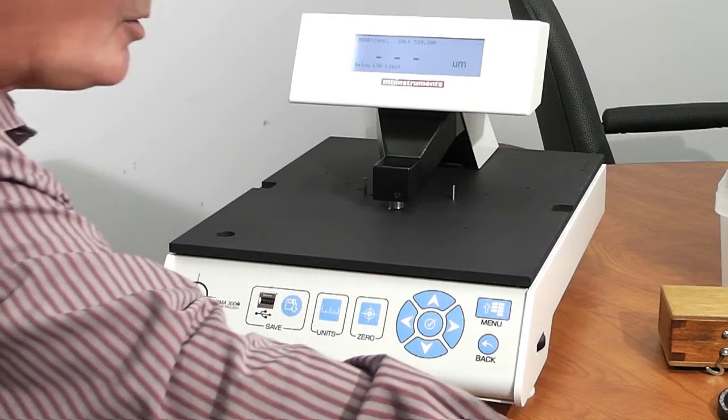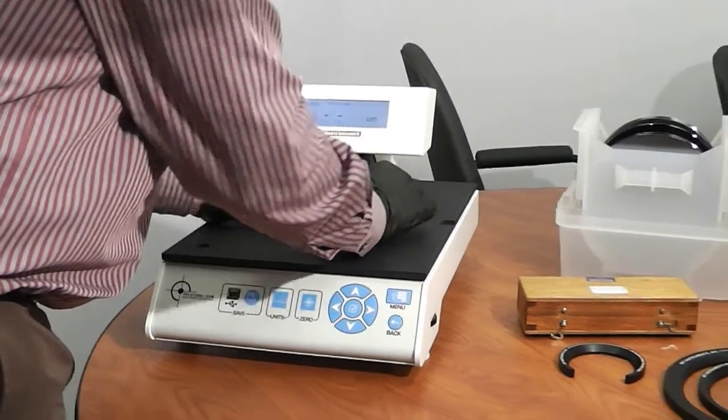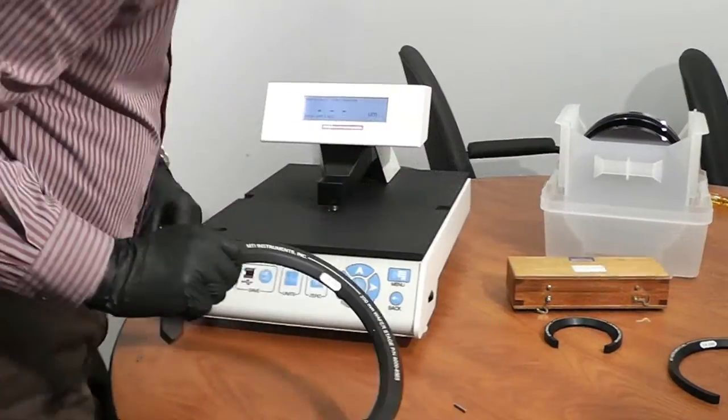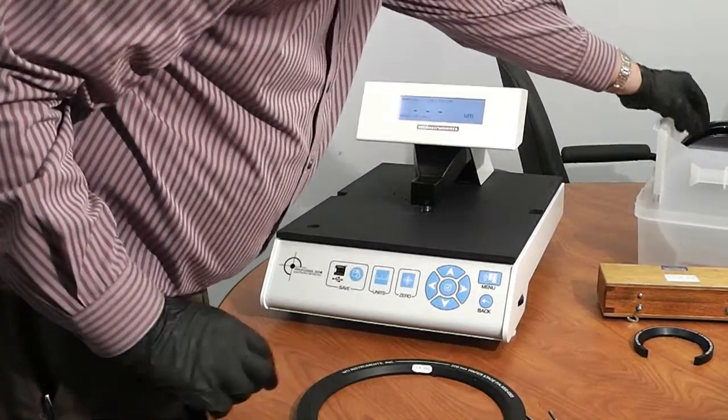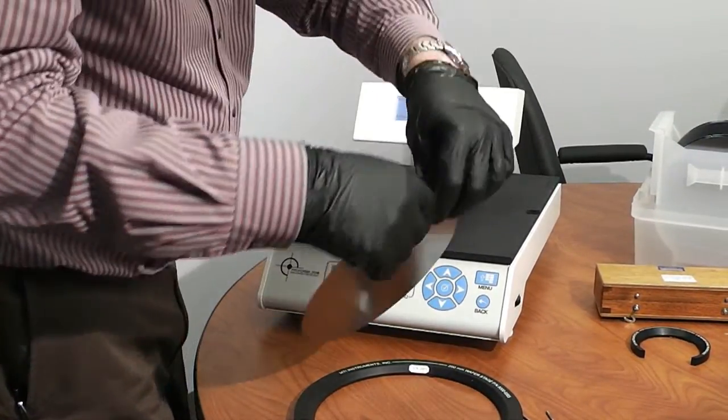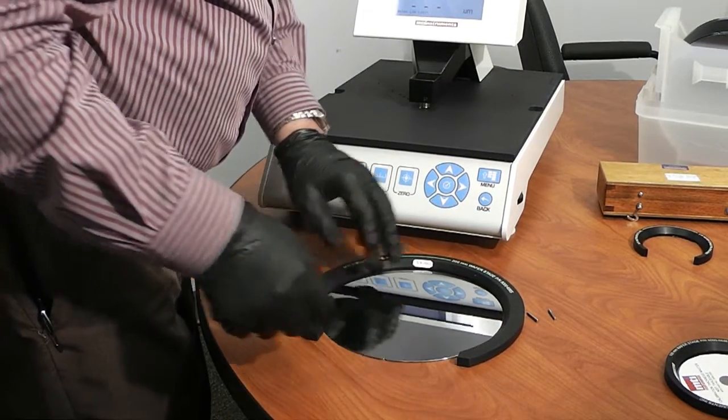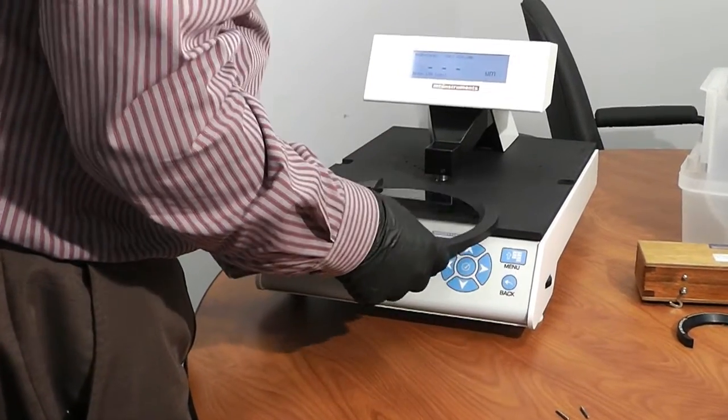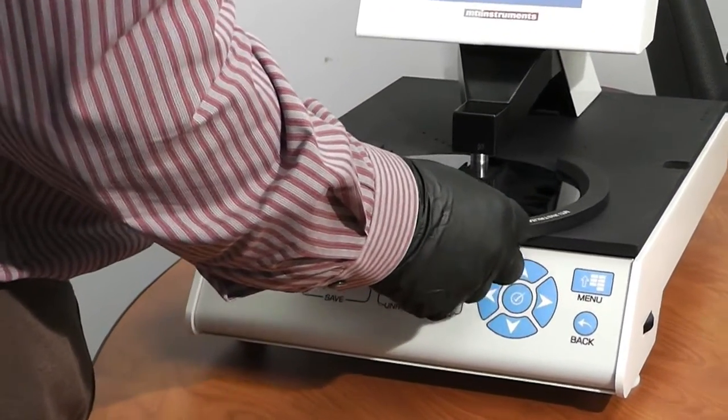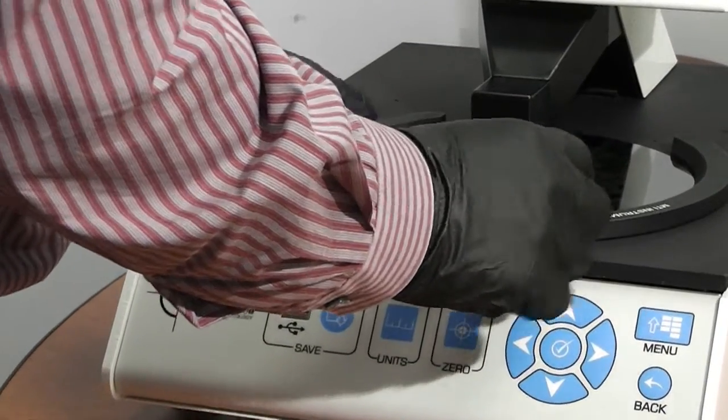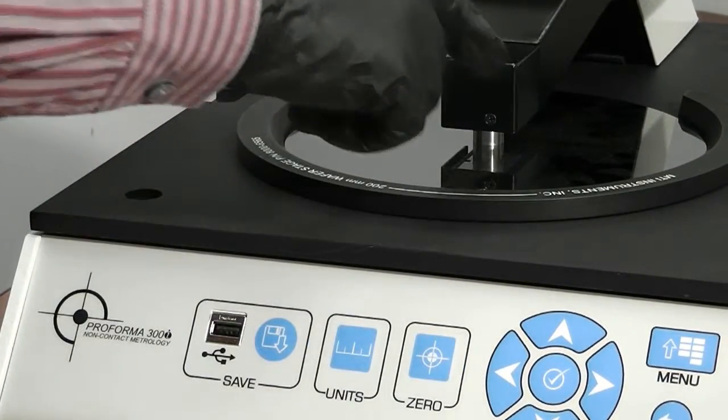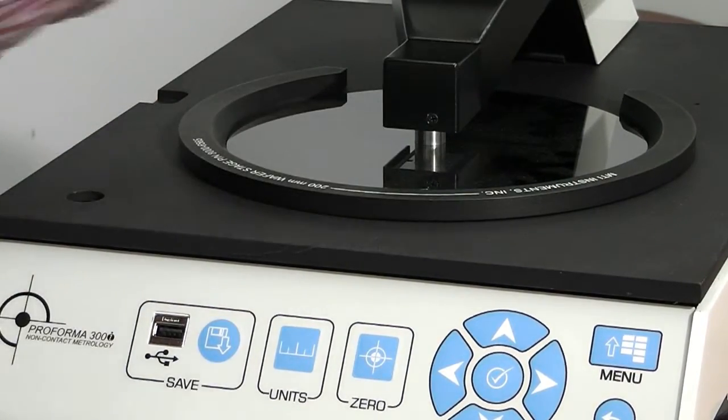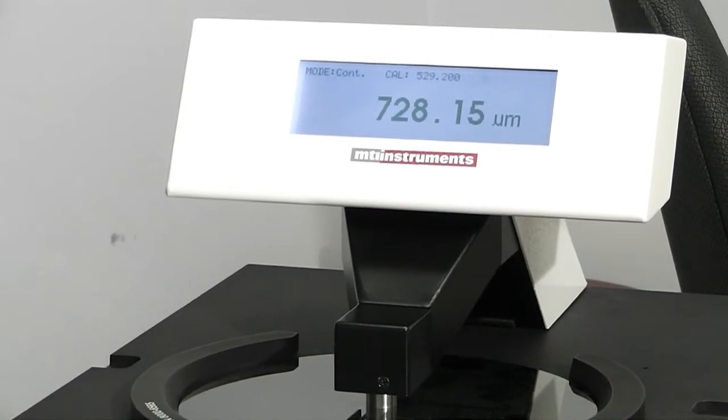And next we'll measure a 200-millimeter wafer. We have a 200-millimeter wafer ring that we're using here. All right, and what I should do is put the pins in to center this, but for brevity here, we're just going to look at the center here. And we can see that this one is 728.15 microns.